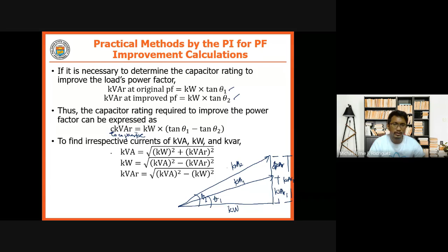Ayan, so solve tayo ngayon ng power factor. Assume that your load withdraws 80 kilowatts and 60 kVARs at 0.8 PF. And then it is now required that this PF is to be improved from 0.8 to 0.9. So determine the amount of the reactive power to be provided by using the capacitors.